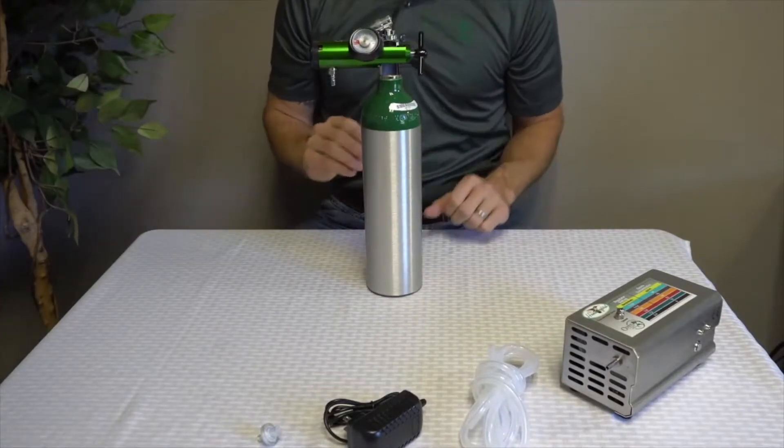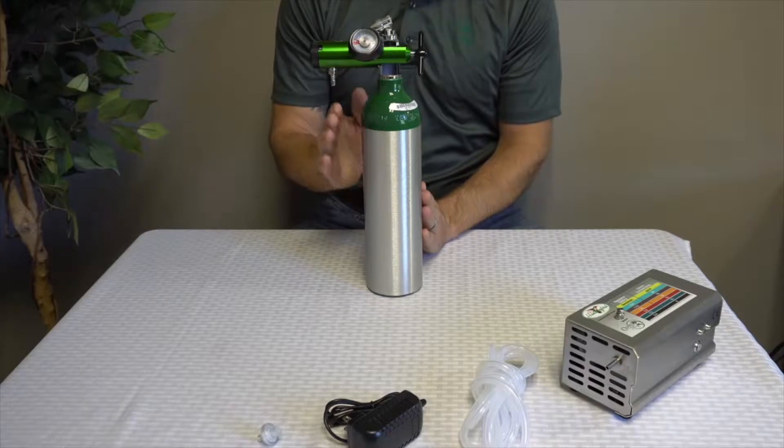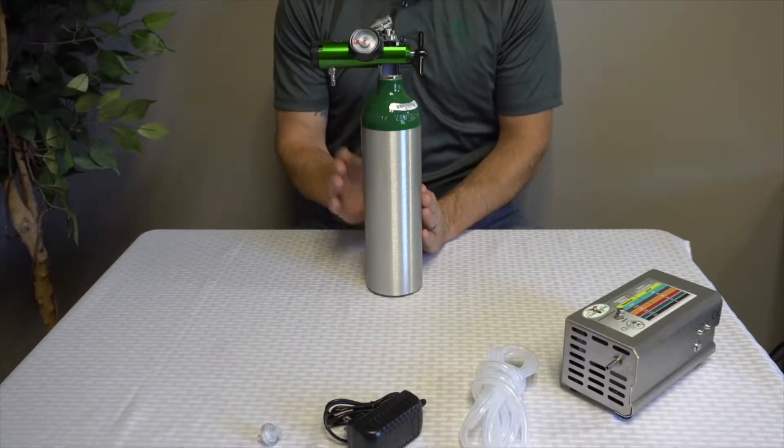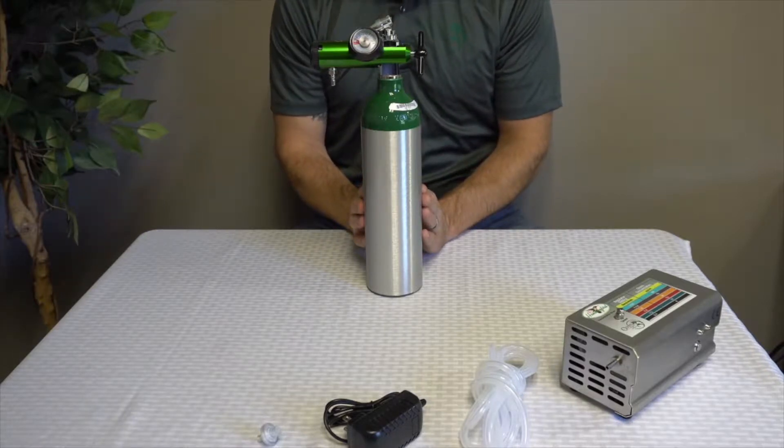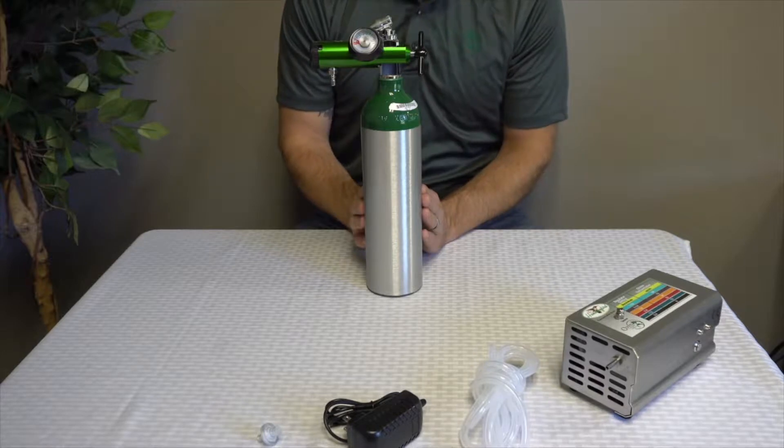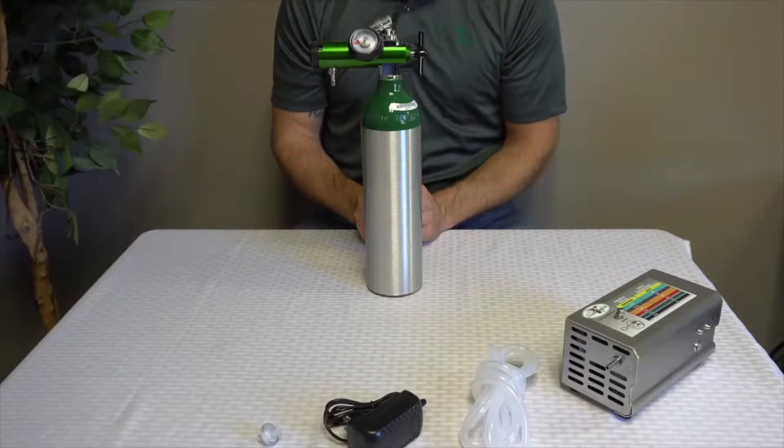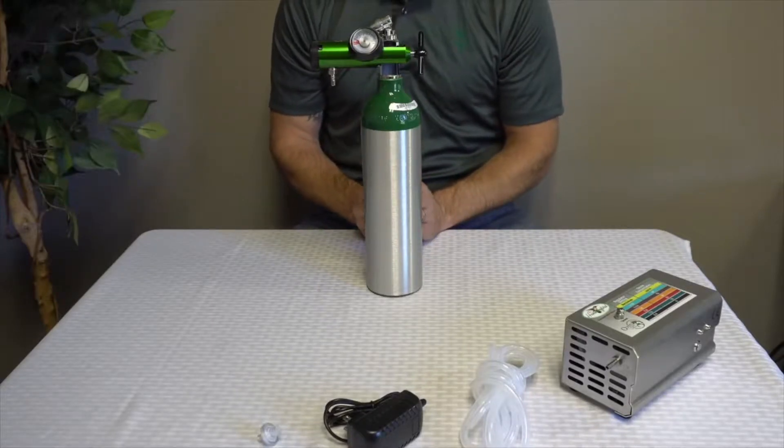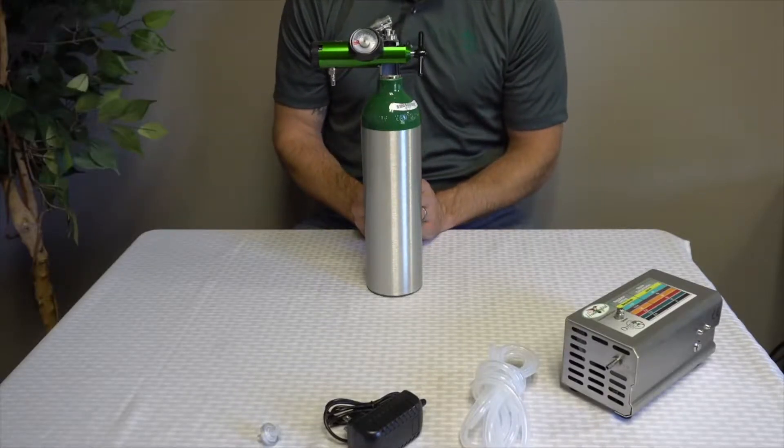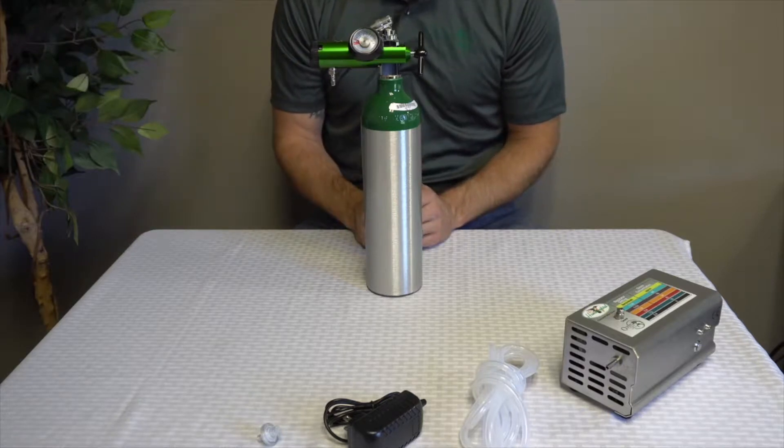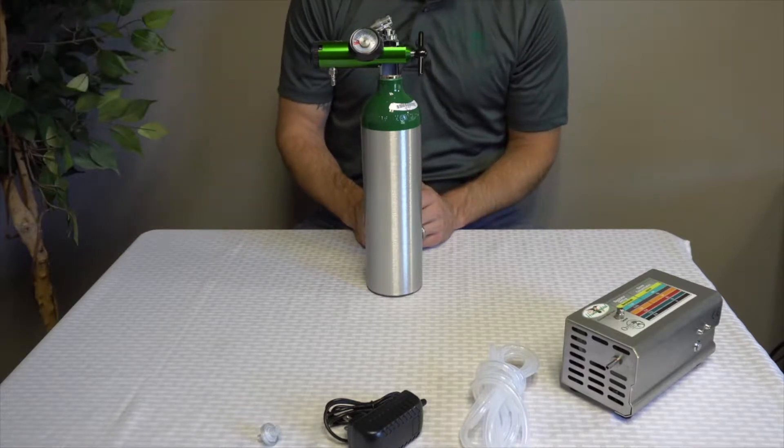One note: you can use a medical oxygen tank as you see here. If you do that, you'll need a prescription from a veterinarian or a doctor to get oxygen. The other option is to use an industrial oxygen tank, which does not require a prescription. They both use the same oxygen; it's just that the medical tanks are validated more stringently as far as the purity goes.